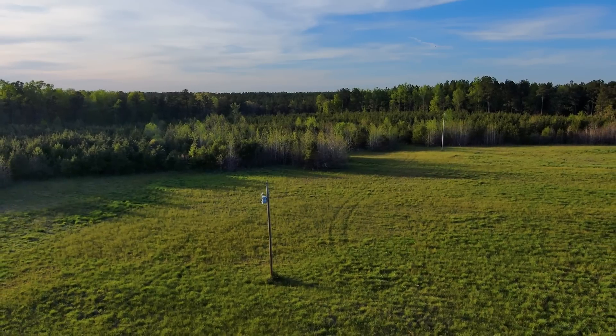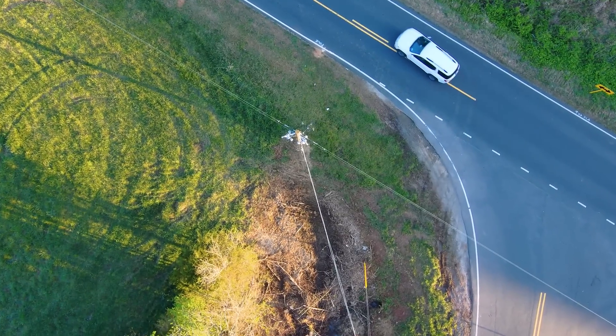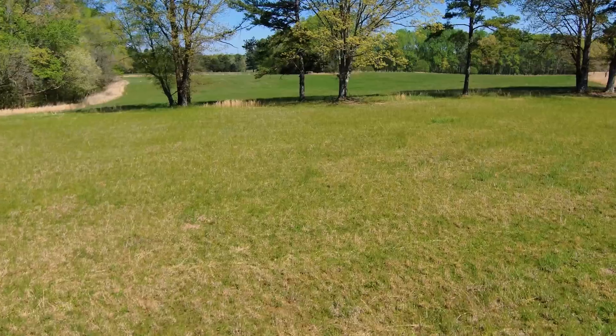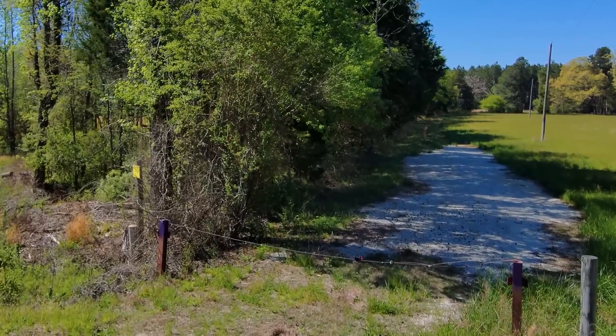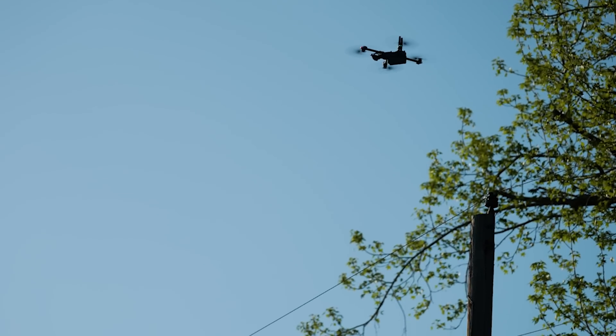For the most part, most utilities don't inspect the tops of poles because it's pretty labor intensive. The legacy methodology is a guy in a bucket truck, setting up on each pole, which is very time consuming. These poles are along the side of a road so access isn't an issue, but back there at the corner where that line cut across the pasture, you've got gates to open and close, off-road conditions. When you start getting into those more rural areas, the time on target is already significantly higher — you're looking at 15 to 20 minutes to get a thorough inspection comparable to what we're doing with a drone.